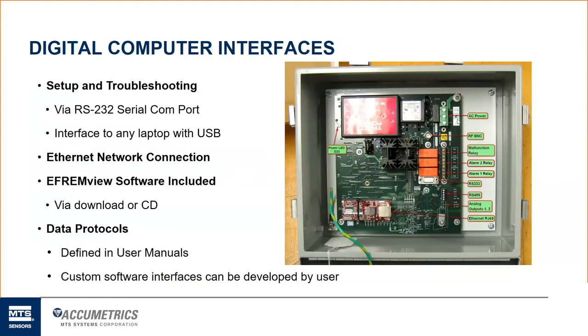Up in the top right is the AC or DC power input into our electronics. As long as that power is brought into our receiver, the telemetry system is going to be functioning. And these orange blocks here are the Form C contact relays. That's why that first one, the malfunction alarm, is a normally closed contact, so that if there is a loss of power or any interruption, it'll open that normally closed contact, allowing the user to know there's an issue with the telemetry system. The next two orange blocks are alarm two and alarm one, the warning and ground fault alarm. And then there are some other terminal block interfaces for the analog 4-to-20 current loop outputs.